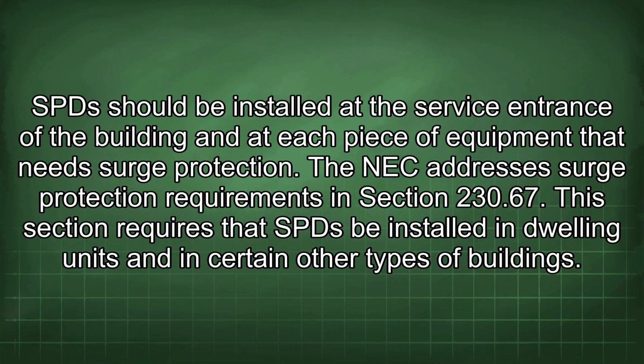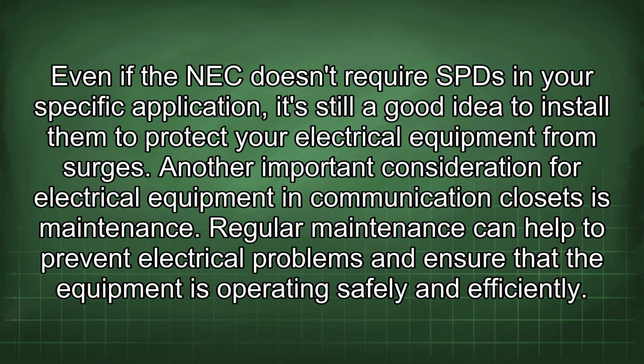SPDs should be installed at the service entrance of the building and at each piece of equipment that needs surge protection. The NEC addresses surge protection requirements in section 230.67. This section requires that SPDs be installed in dwelling units and in certain other types of buildings. Even if the NEC doesn't require an SPD in your specific application, it's still a good idea to install them to protect your electrical equipment from surges.